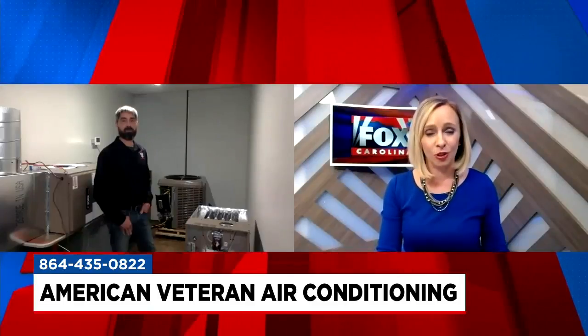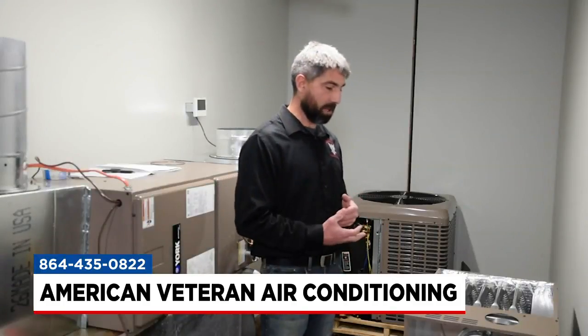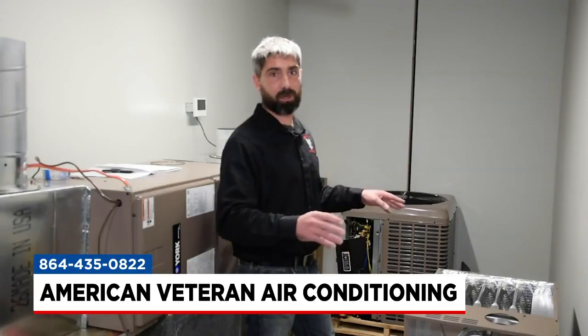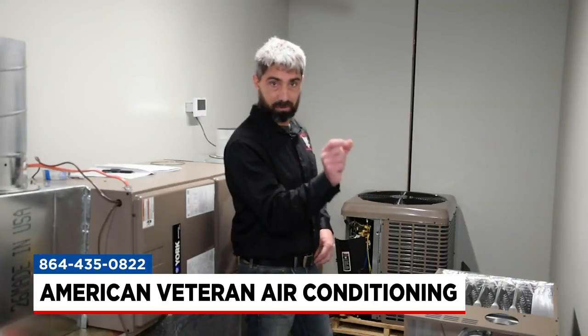So while a certain amount of ice is normal, when is ice buildup becoming a big problem for heat pumps? When ice becomes a problem depends on the atmosphere we're operating in. In just normal cool weather — 40, 35, 30 degrees outside — there should be no ice on that outdoor unit. If there's legitimate layered ice built up on that unit, there's a problem with the unit.